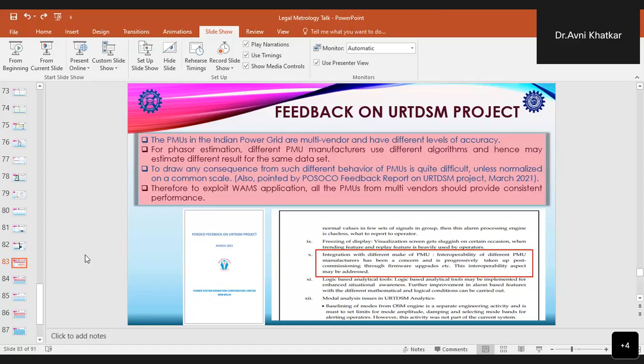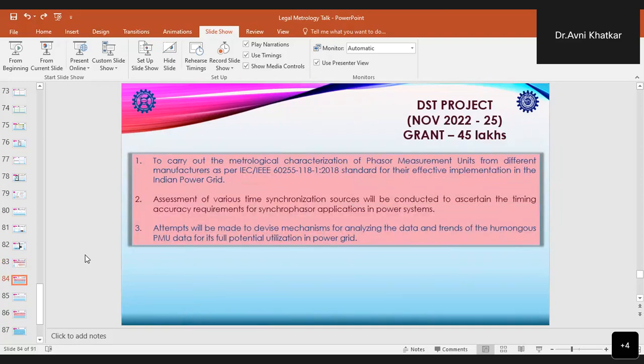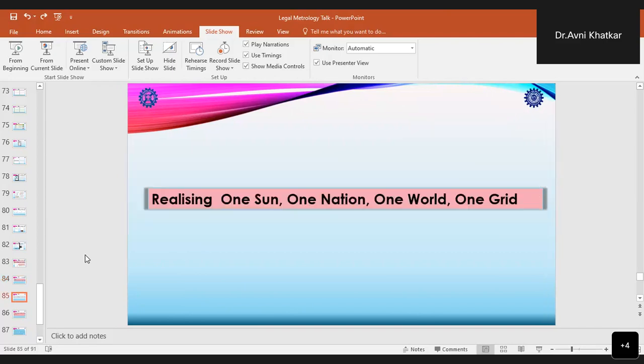So on the basis of this feedback, we are also undertaking a DST project of 45 lakhs in order to carry out the metrological characterization of these PMUs from different manufacturers as per the latest IEEE standard for their effective implementation in the Indian power grid. Also in this, assessment of various time synchronization sources will be conducted in order to ascertain the timing accuracy requirements for the synchrophasor applications in the power systems.